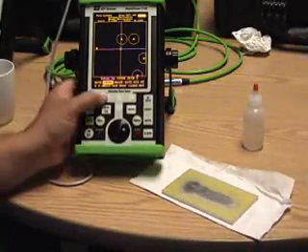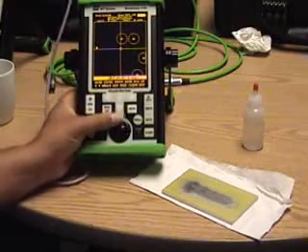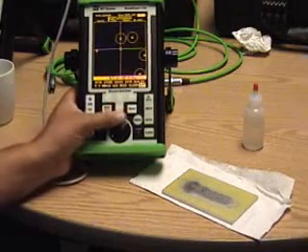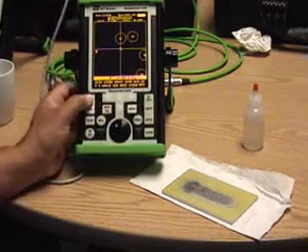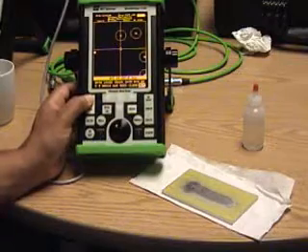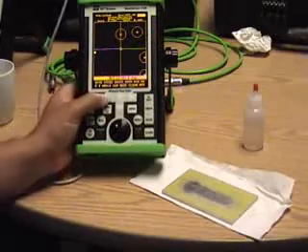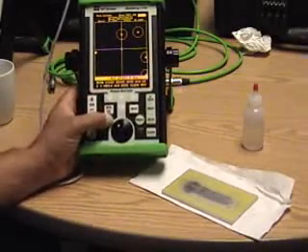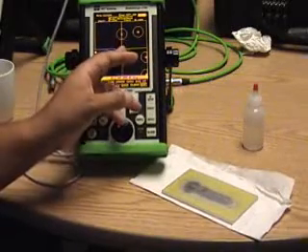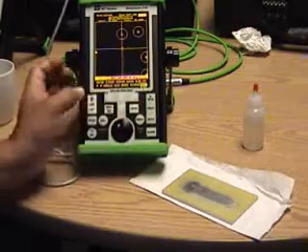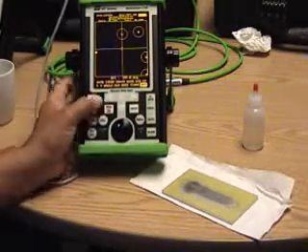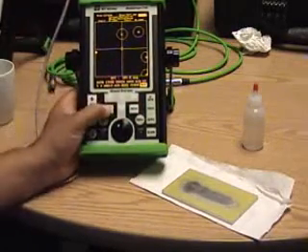Then I will go ahead and finish my rotation and gain. Now, to increase separation, I am increasing gain, but we are moving everything off the screen. So, to compensate for that, we can actually move our zero position in the center of the screen. Zero position is not the same. It is different than null.